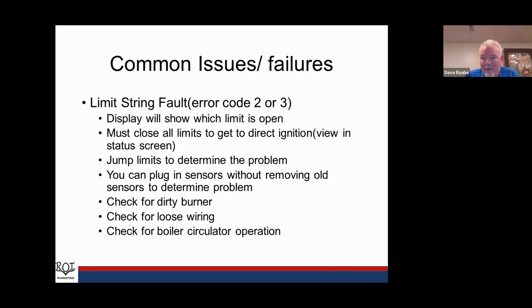The other thing is to check for loose wiring. Anytime we're dealing with limits or sensors, I always go through and make sure we don't have loose wiring. If the limit that is not closed is our flow switch, then on the water side, I probably want to check for boiler circulation, make sure that circulator is operating. And you can do that with your meter. You can put the amp meter on, make sure it's drawing the proper amps.